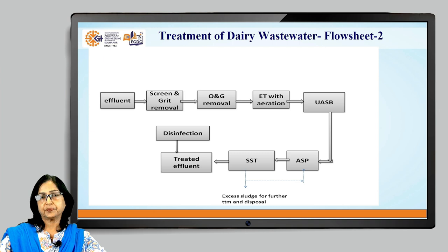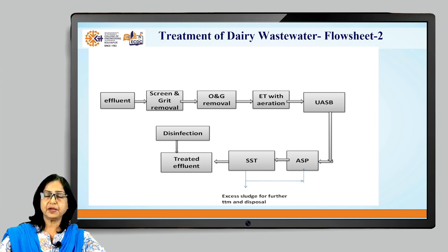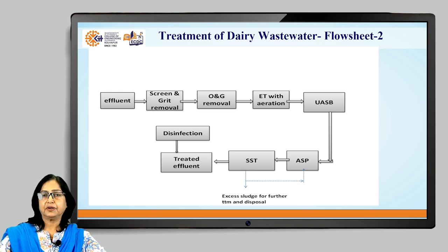In the second flow sheet, after screen, grit removal, and oil and grease removal, the wastewater is taken to an equalization tank with aeration, and from there fed to a secondary system consisting of UASB (upflow anaerobic sludge blanket) followed by an aerobic step. The settling step is skipped because UASB handles that, and it also offers the option of biogas recovery. The effluent is further treated aerobically — activated sludge process followed by a secondary settling tank — and the supernatant is disinfected and ready for disposal.